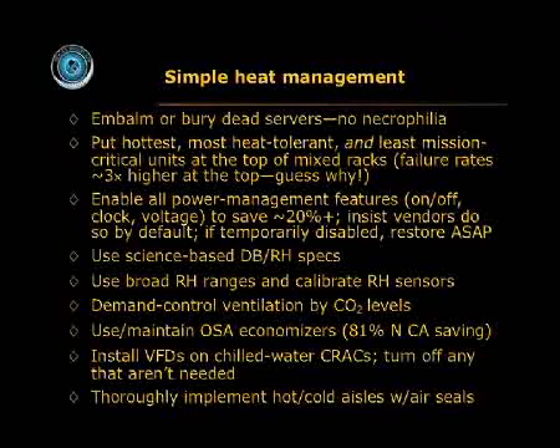Either embalm or bury dead servers. We have these zombie servers that arise and walk in the night. They're on, but they're not doing anything. We should put the hottest and most heat-tolerant and the least mission-critical units at the top of mixed racks. Why is it that failure rates are 3 times higher at the top than at the bottom of the rack? It's because heat rises. And yet we often just put things in randomly without this sort of prioritization.